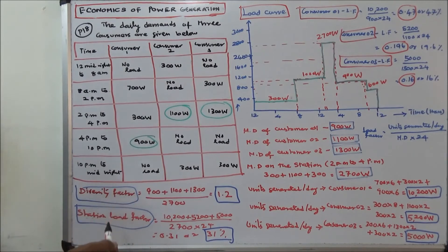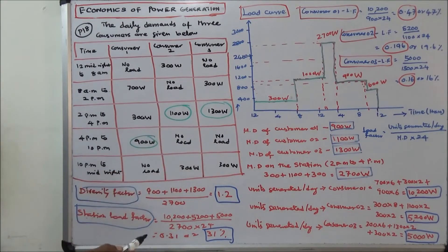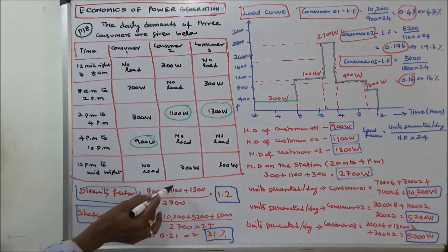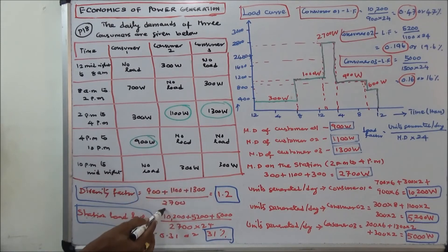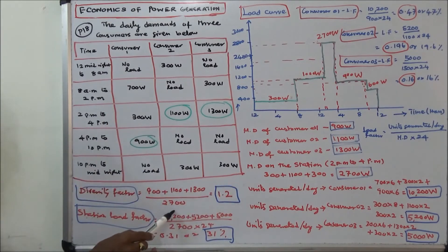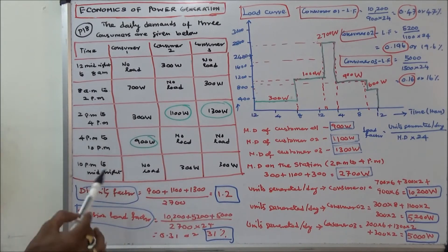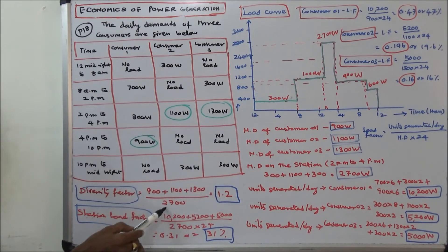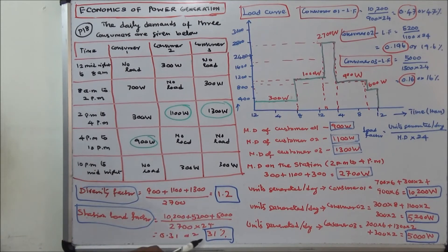Diversity factor equals sum of individual maximum demands divided by maximum demand of the station. So: 900 + 1100 + 1300 = 3300 divided by 2700 = 1.2. Station load factor equals total units generated per day divided by maximum demand of station times 24: (10,200 + 5,200 + 5,000) ÷ (2700×24) = 0.31 or 31%.